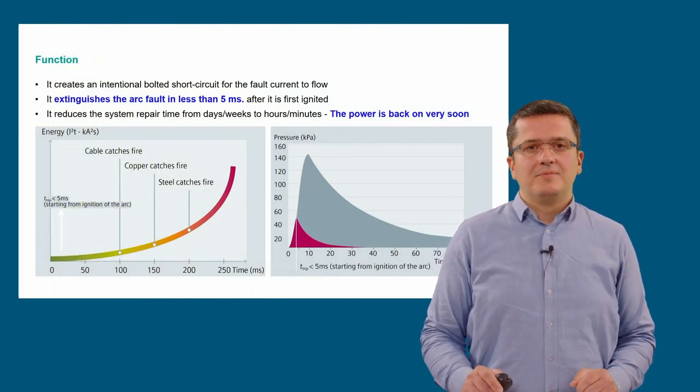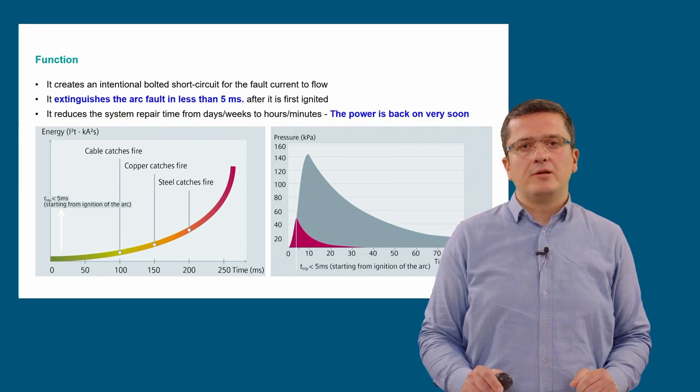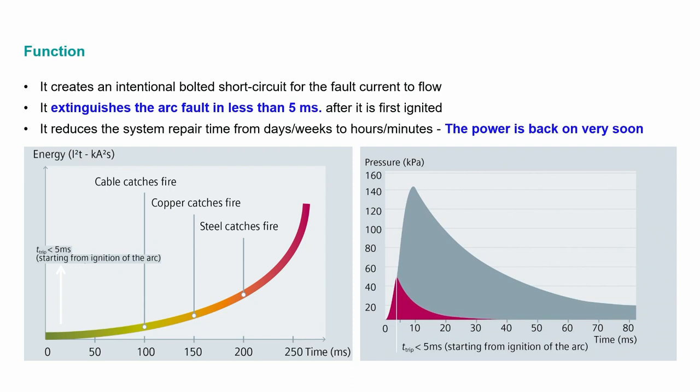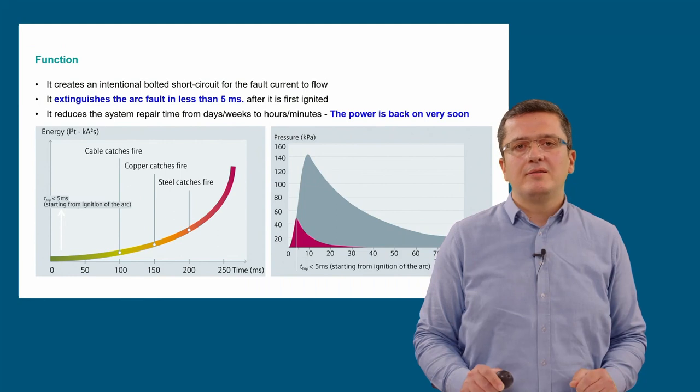So, SIQuench, in the case of an internal arc, by consciously closing the live bus bar over the ground bar of the switchgear, creates a controlled, bolted short circuit path for the fault current to flow. This is the main current path of the switchgear and is actually the intended current path for such fault conditions. And it does that within five milliseconds after the arc is first ignited. By doing so, it prevents the damaging effects of an arcing fault and allows to re-energize the switchgear in a very short time, avoiding time-consuming and costly system repair activities.